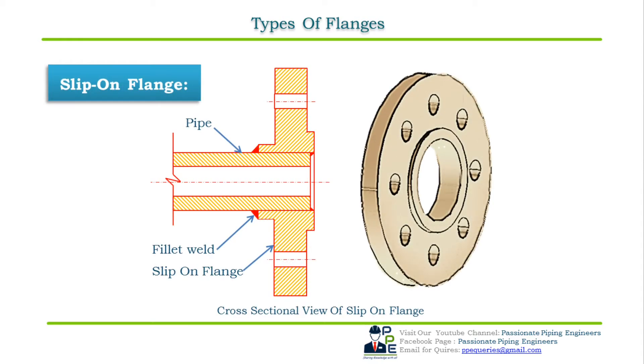The next type is the slip-on flange. A slip-on flange is connected to the pipe or fittings by two fillet welds — one executed inside and the other outside the cavity of the flange — to provide sufficient strength and prevent leakage. The pipe is set back from the face of the flange at a distance equal to the wall thickness plus 1/16 inch. Slip-on flanges are manufactured with an inside diameter slightly bigger than the pipe OD so they can slip over the pipe. The calculated strength under internal pressure is about two-thirds that of the weld neck flange, and fatigue life is one-third.